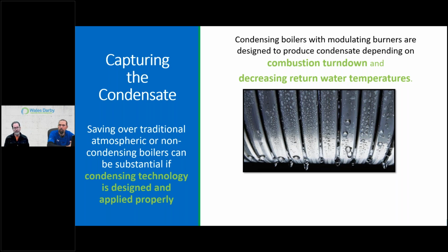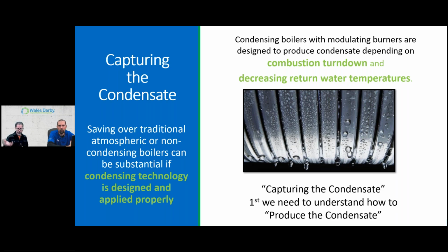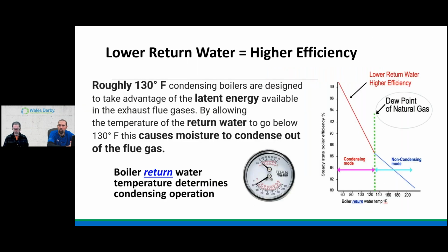With condensers, when I make domestic hot water, that's not good enough in my book. I want to see something in the 90% and not the low 80s. So just go back to oil then. Yeah, for a floor-mounted atmospheric. So the truth is, capturing condensate sounds all good and well. It's like, yeah, first we need to understand how to produce it, right? And that's, again, that change. If you're not doing this or refuse to look at it for whatever reason, well, you're going to be left in the dust. All right, so lower return water equals high efficiency.